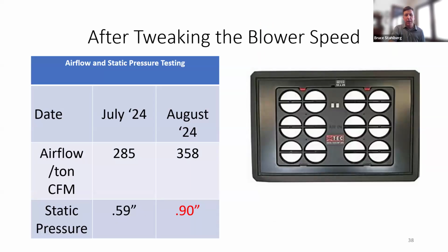So here's what happened. We tweaked the blower speed. We remeasured it. We got it up from 285 to 358 per ton. Notice the static pressure went up as well. The problem with this system was that the air conditioning system was way oversized, but we weren't changing the air conditioner. We were just doing the furnace. So we had to struggle with that. I've been told that the airflow is more important than static pressure, so we had to kind of live with it. I just told the owner that when they replace the air conditioner, they should resize it.